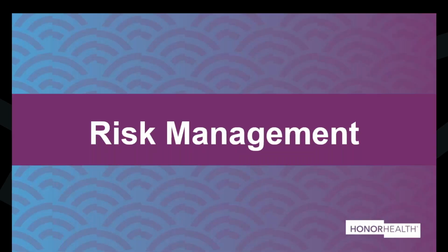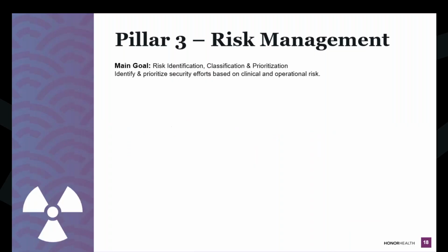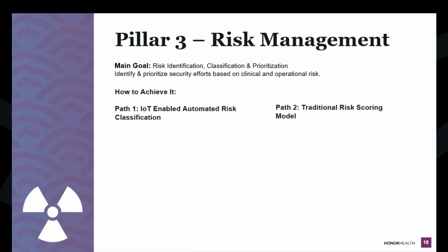Risk management, arguably the most challenging area when it comes to medical device security. So our goal here is to identify the risk, classify the risk, and prioritize what that risk looks like. And of course, you want to make sure that there's no operational impact when it comes to some of these things. So again, I'm going to give you two options here. You have your automated path, and then you have your traditional path. The traditional path includes building your own scoring model, or you perhaps take a scoring model that's already published.